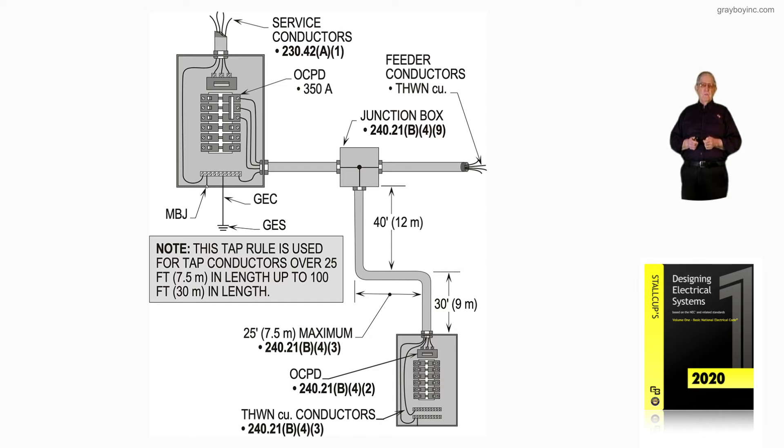Notice we have a 350 amp main ahead of that feeder. We have a junction box that complies with 240.21(B)(4) item 9. Notice we're tapping with smaller conductors, and the minimum size tap that could be made in this over 25 foot up to 100 foot run is number six. The tap conductors meet 240.21(B) item three, and the overcurrent protection device where the tap terminates to the main in the panel board is 240.21(B) item two.